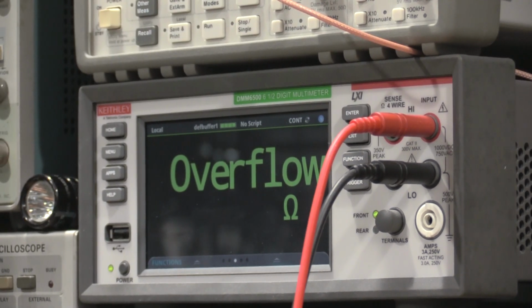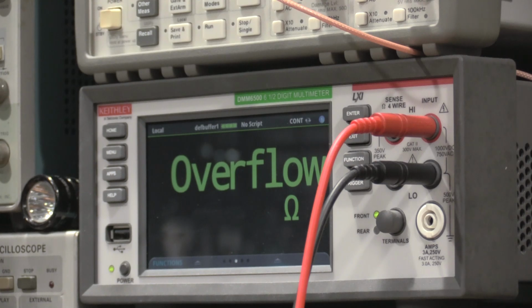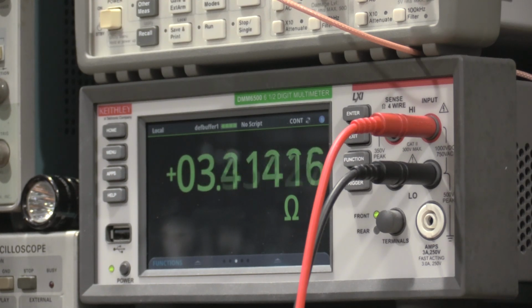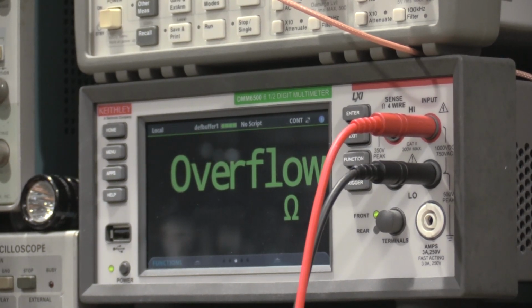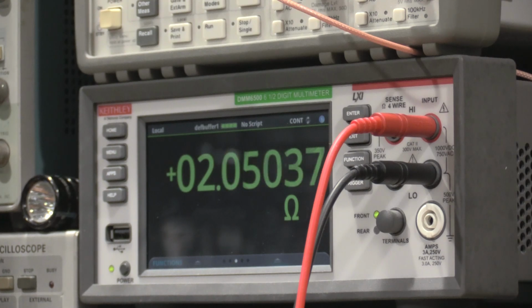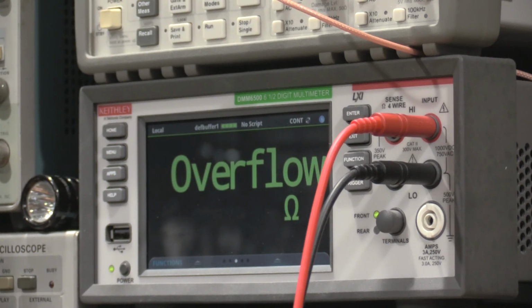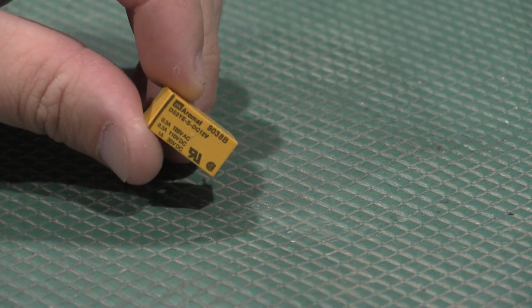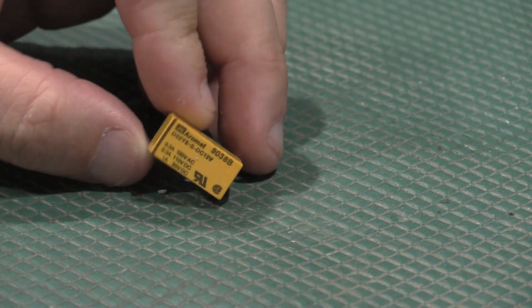Okay, with the relay removed, we'll check the normally closed contacts again. That doesn't look healthy, like at all. 1.2, 2 ohms, that's not healthy. Other side, 1.52. So this relay has got some problems. Well, I don't want to say this is the problem, but it is definitely a problem. I'm going to have to see if I can find one of these and source this part.